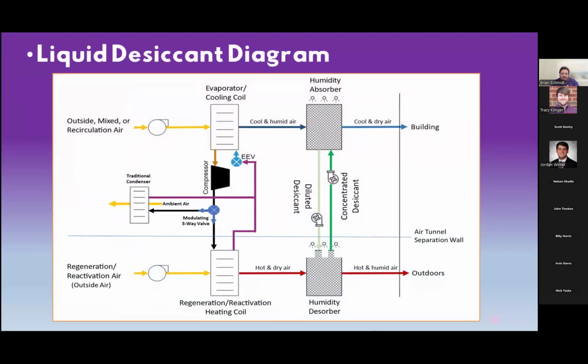For those of you that like diagrams more like this, same exact thing. We're bringing the outside air in at the top on the left through the evaporator coil. Our compressor, we have a 3-way modulating valve. So the hot gas off the compressor can either go through our traditional condenser or it can be rerouted to that regeneration or the hot gas reheat coil. Again, this valve determines how much of that hot gas we send over the reheat coil, which determines how hot that temperature is, which determines how much moisture we can evaporate from the solution, which again determines the concentration. So on days where we need more dehumidification, we're going to provide more hot gas to that reheat coil, therefore providing hotter air temperatures to evaporate more of the moisture from the liquid desiccant. On days where we don't have nearly as much of a dehumidification need, we're going to send the vast majority through our traditional condenser.